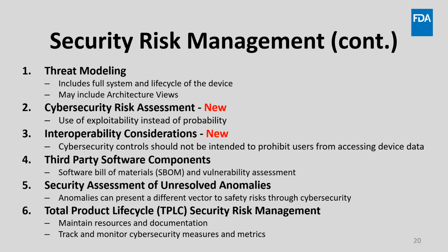For third-party software components, this is where we outline our recommendations for the software bill of materials, support and end-of-support information, and the vulnerability assessment for those third-party software components. We also recommend that you provide a security assessment of unresolved anomalies. This is because anomalies can present a different vector to safety risks through cybersecurity causes. Finally, we make recommendations around total product lifecycle security risk management, where we recommend that you maintain resources and documentation throughout the lifecycle of the device, and that you track and monitor cybersecurity measures and metrics in order to track how your system and processes are performing.